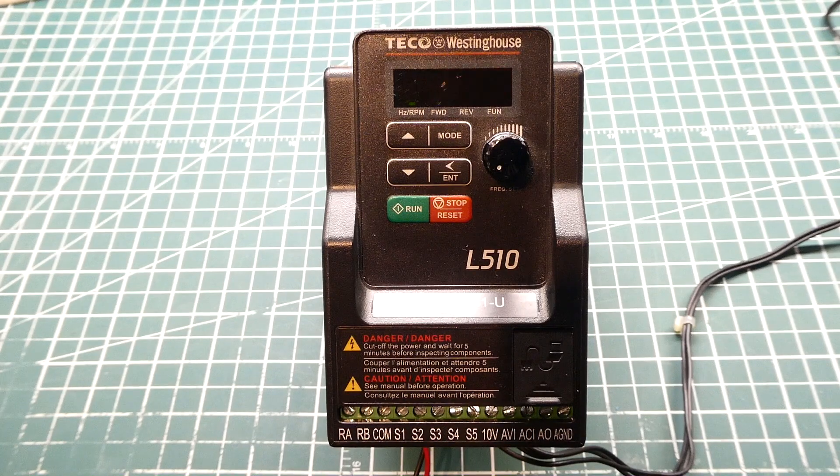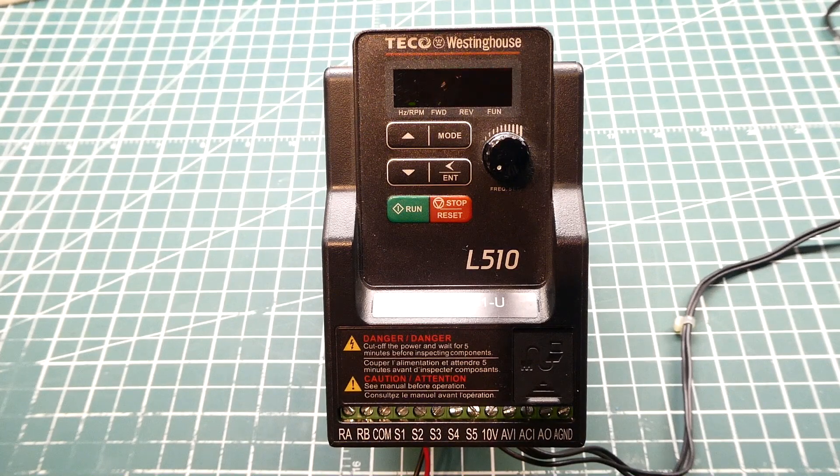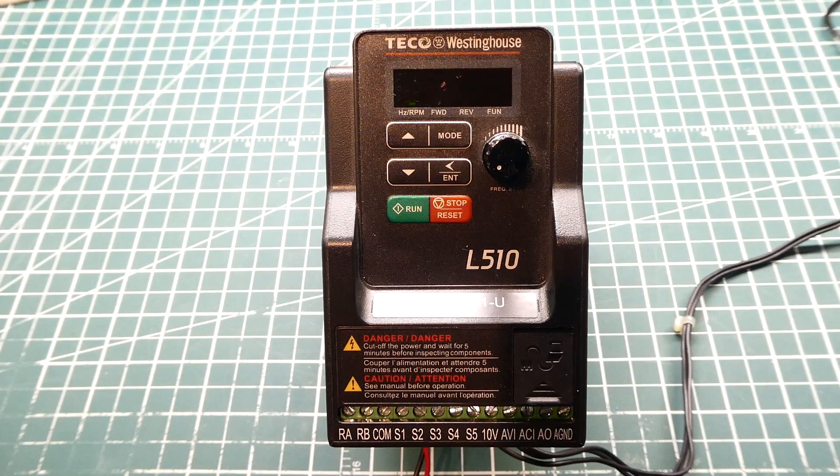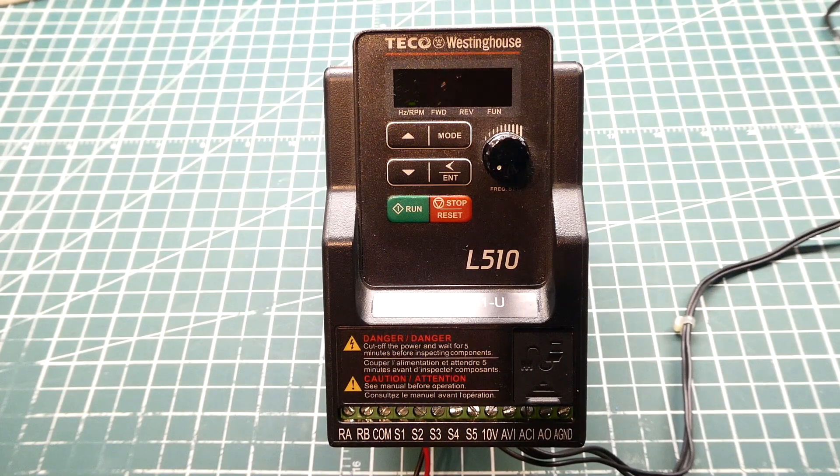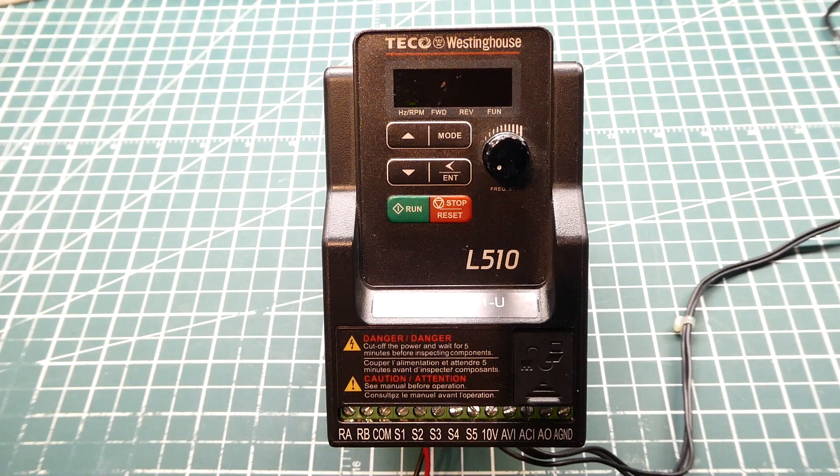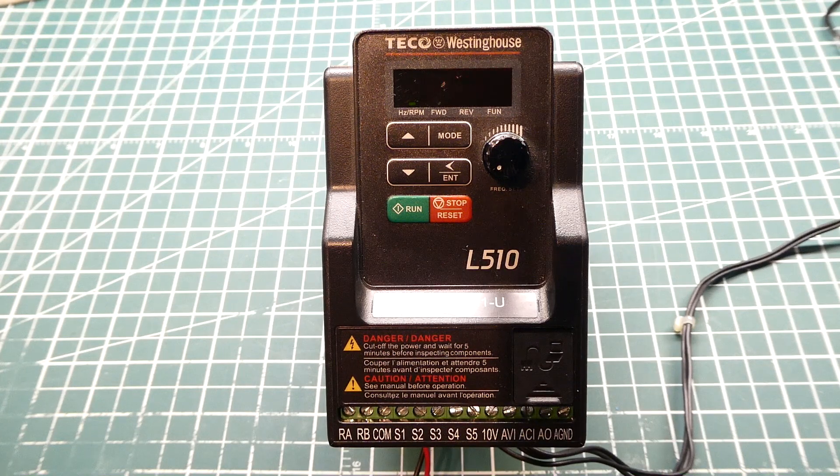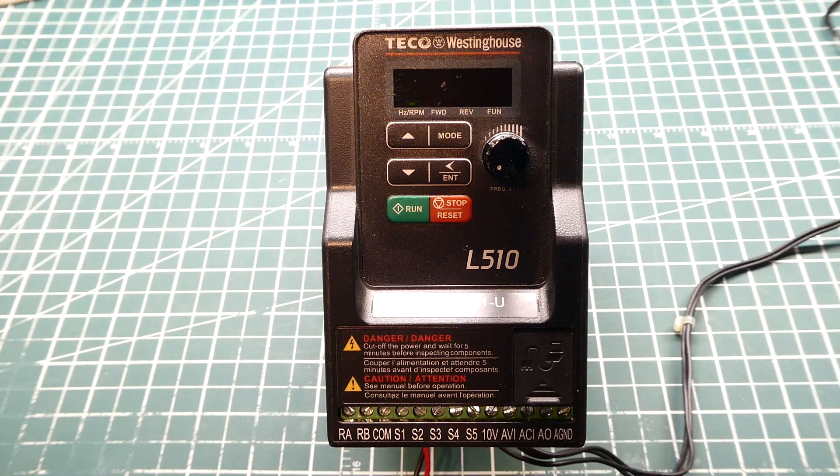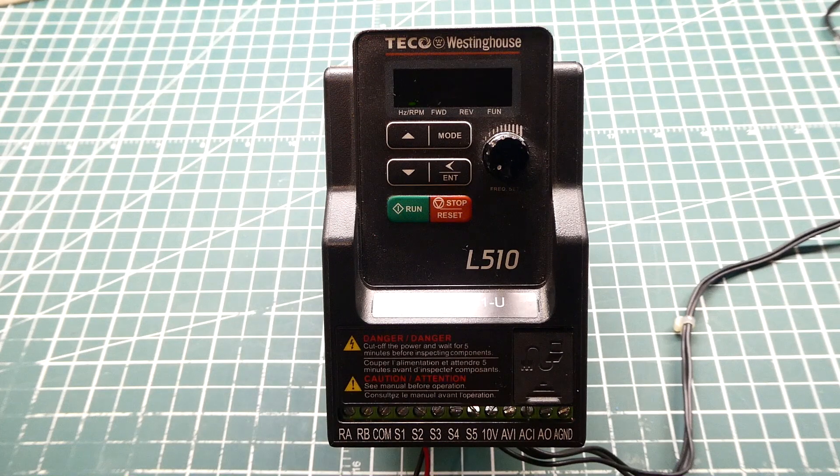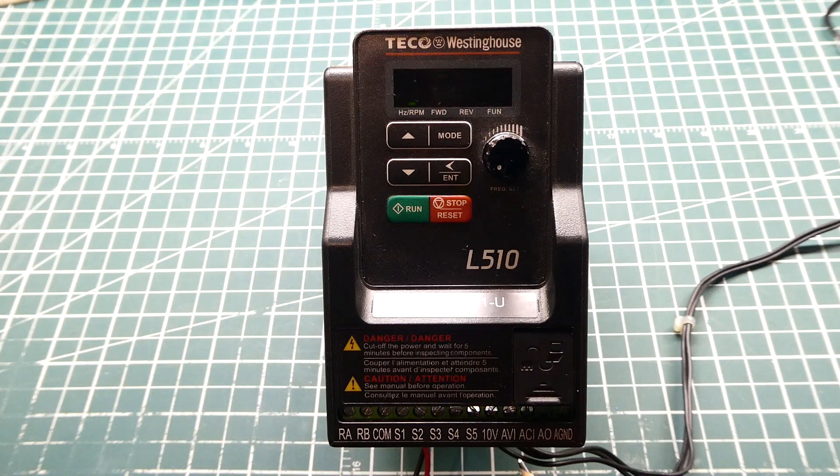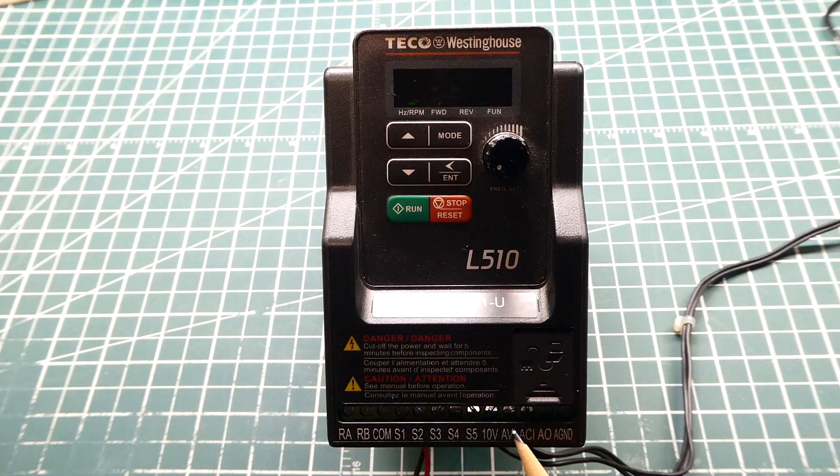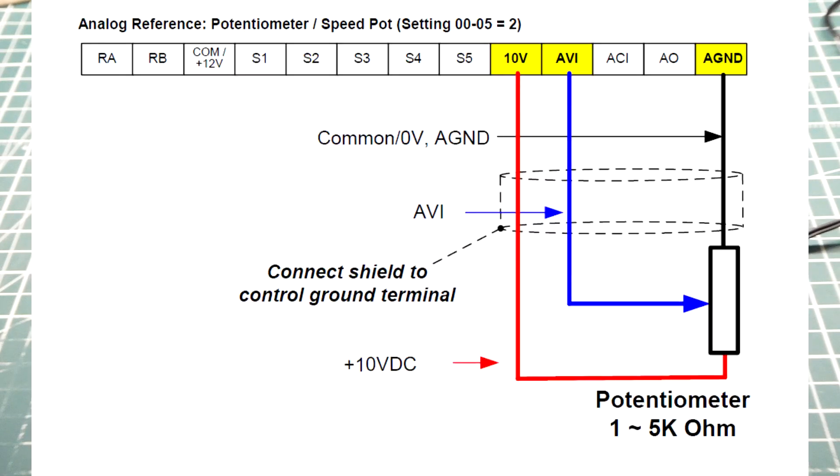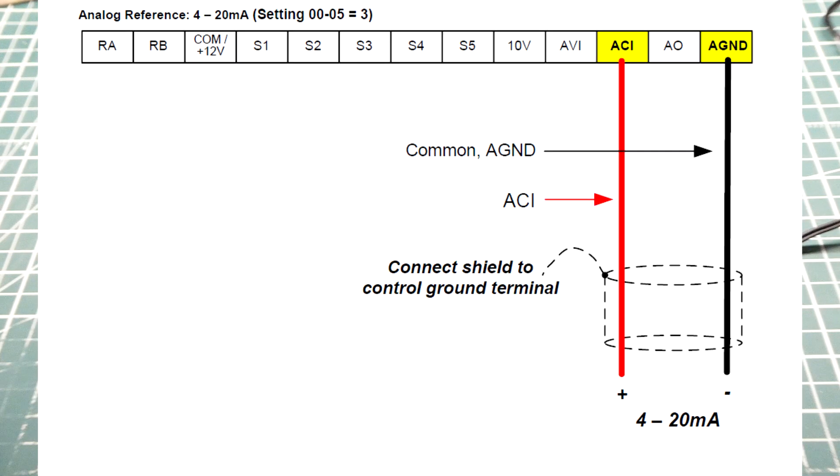Okay, I have my variable frequency drive on my bench powered up. Now there's three ways we can control the speed and direction of a three-phase induction motor using a variable frequency drive. If you look at the terminal strip, you can see there's an AVI input that's 0 to 10 volts, so we can control the speed of the motor by feeding 0 to 10 volts into the AVI pin.